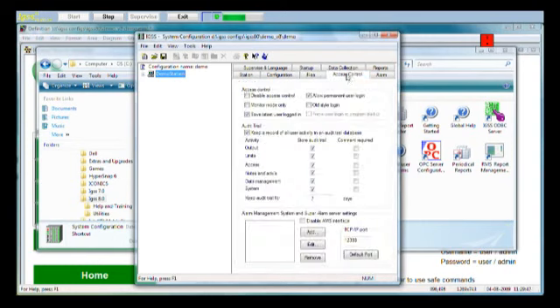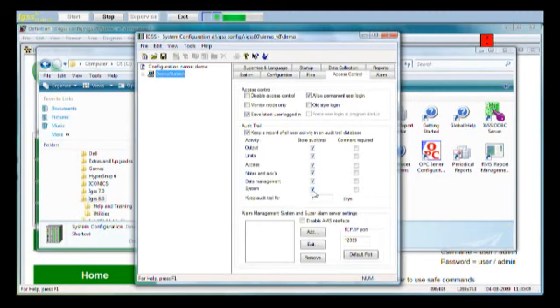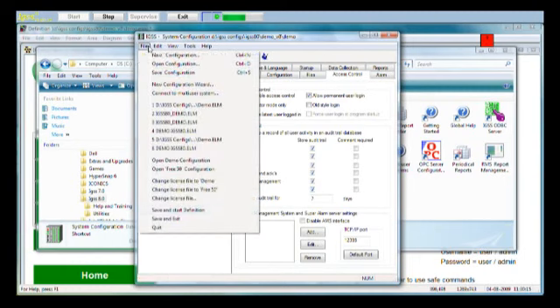That's it for setting it up. And on the access control tab we have two different things we need to do. We must make sure that this checkbox, disable access control, is not selected because we want user administration to be active. And then under audit trail we will say keep a record of all user activity. And we will make sure that all these checkboxes are enabled so that all output, limits, acknowledgement, etc. is stored in the audit trail. That's it. We can close down system configuration.